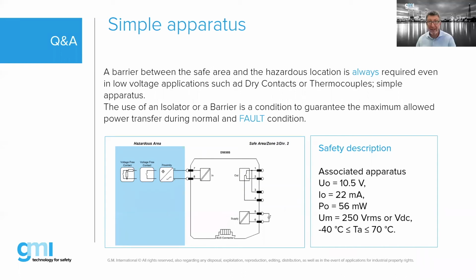You can put it anywhere you like in zone zero, but now you have two wires that come to the safe area. On those two wires, how do you control the energy? How do you make sure that nobody puts enough voltage there? It can be 24 volt, 2 amps, and that would be above the minimum required energy to ignite in certain gases. So that is what the barrier's job is for: to make sure that the power on the other side of the barrier is limited. This is a DI barrier type, so you have 10.5 volt, 22 milliamp, 56 milliwatt.